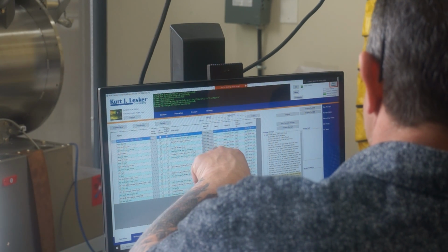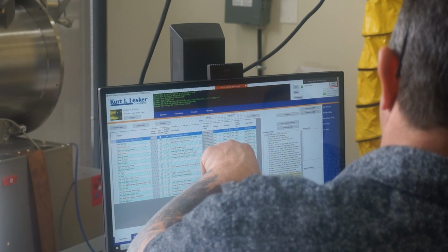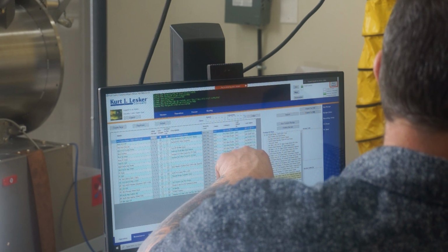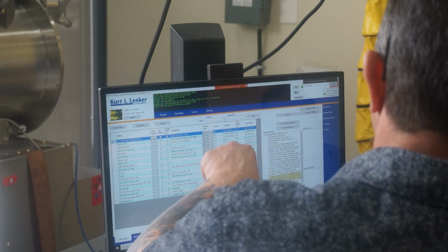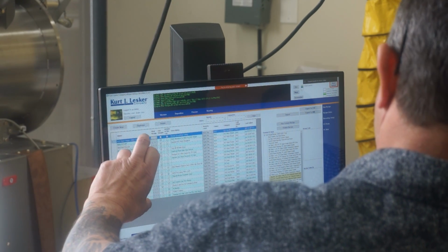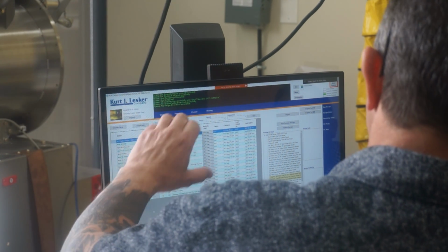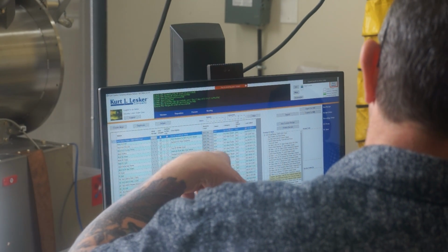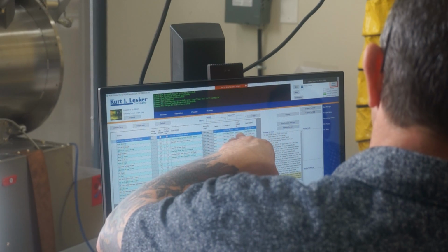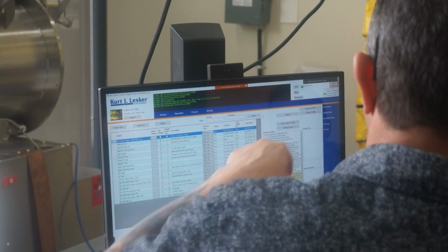Some of the screens you might have where you can filter by signal or by category if you want to. So the interlocks are set up the same way. You only have a small amount of recipes, so you can see everything on the one screen. If you had maybe 100 or 200 recipes, maybe you would filter via signal or category. So that's just your option here.